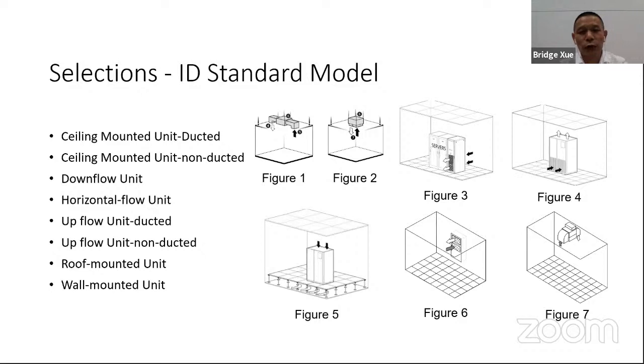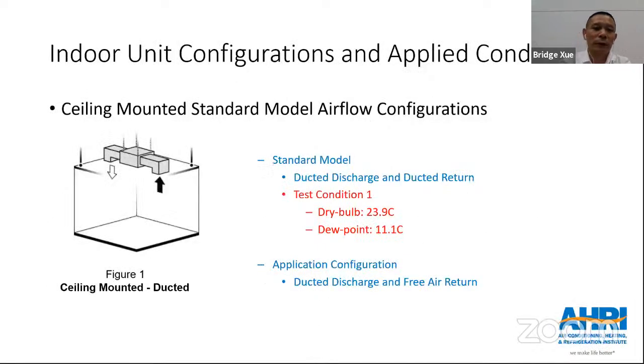I'm going to introduce different applications with different temperatures for these units. The first one is the ceiling mounted standard model airflow configurations. You can see here the standard model is ducted discharge and ducted return. This is condition one that we applied: the dry bulb will be 23.9 and the dew point will be 11.1. The other configuration that may be applied, we call the application configuration: ducted discharge and free air return.